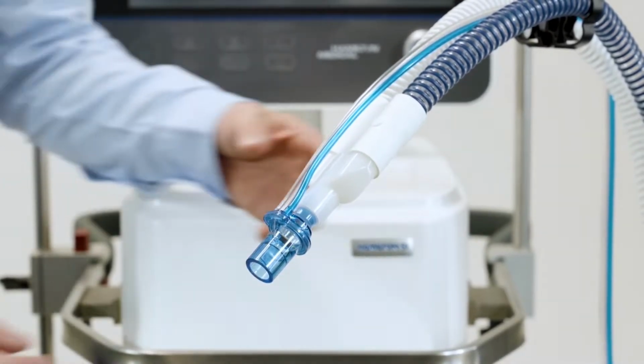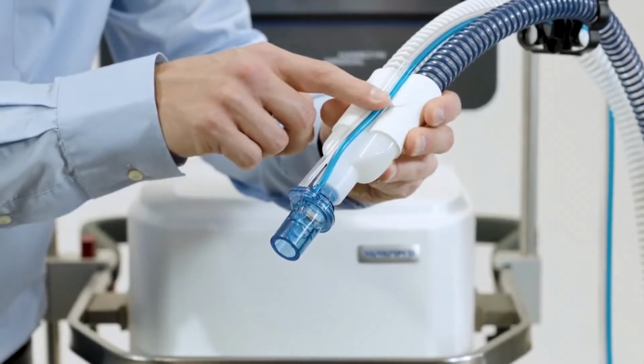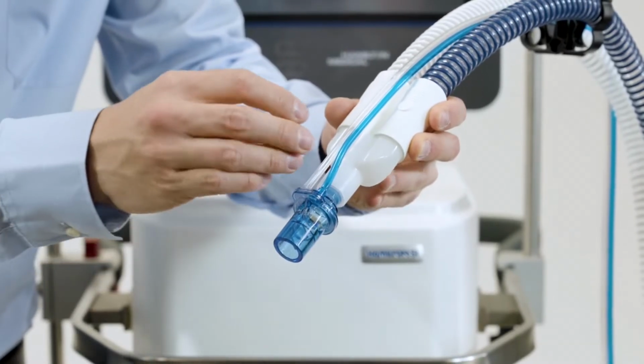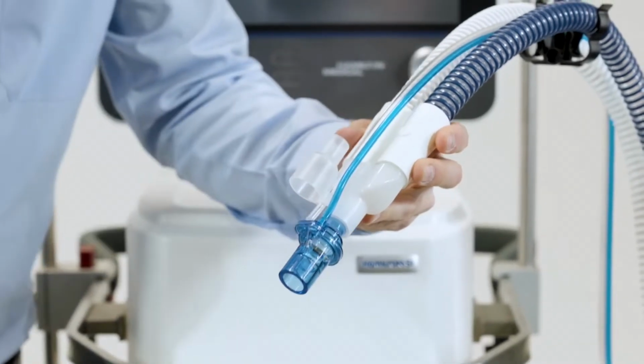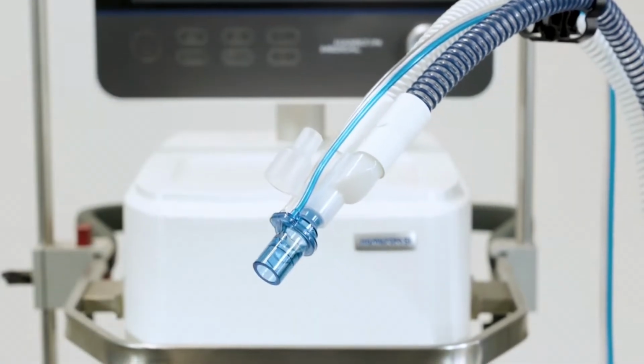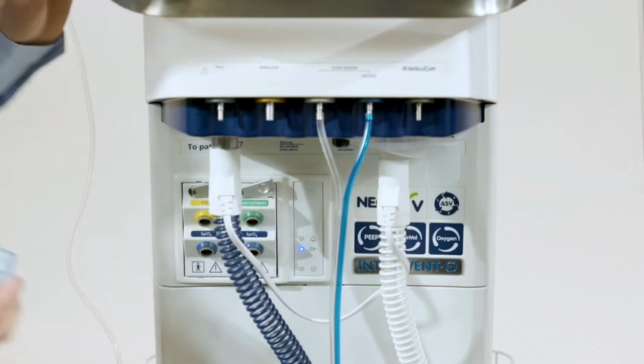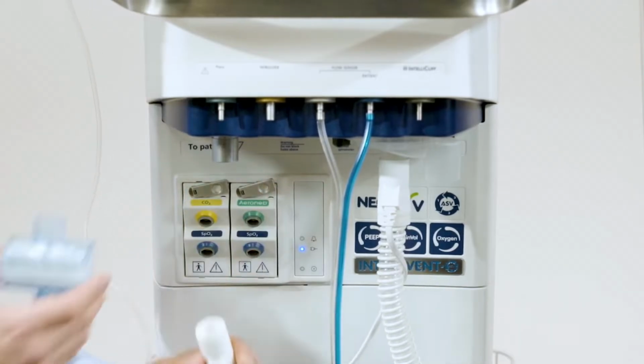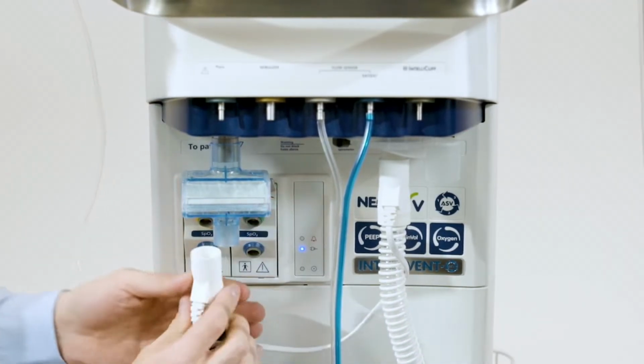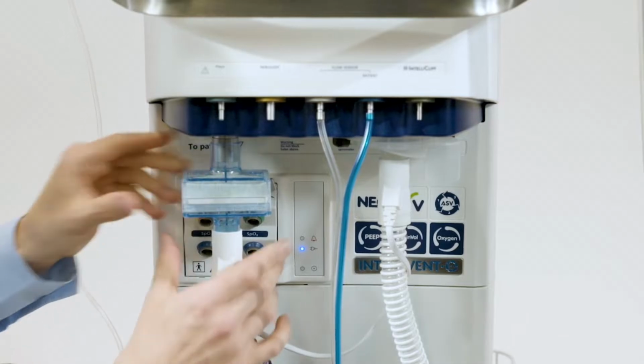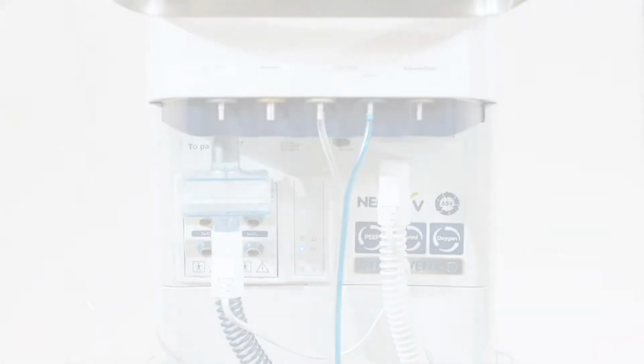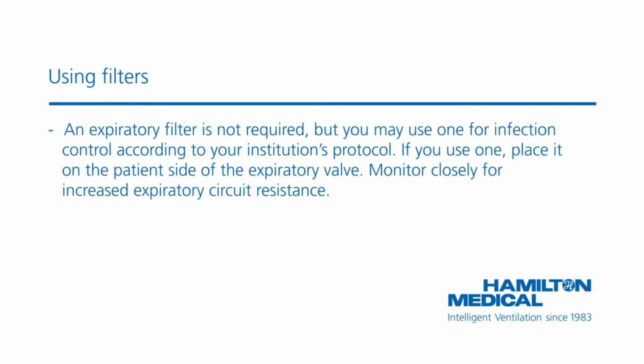The gas temperature is measured at the Y-piece by means of the temperature probe integrated in the inspiratory limb. Keep the inspiratory limb positioned correctly. To prevent patient or ventilator contamination, connect a bacterial and viral inspiratory filter between the patient and the inspiratory port. An expiratory filter is not required, but you may use one for infection control, according to your institution's protocol. If you use one, place it on the patient side of the expiratory valve.